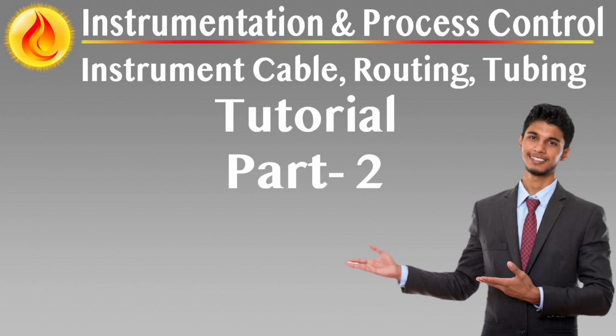Materials must be compatible with their environment. Stainless steel, galvanized steel, or painted mild steel are acceptable. However, galvanized components must not be used near stainless steel process equipment in fire-prone areas due to the risk of molten zinc-induced embrittlement during fire exposure. Trunking shall be side-accessible for cable laying and designed with sufficient clearance above to allow hand entry, typically 0.3 meters for narrow trays and 0.5 meters for wider ones.